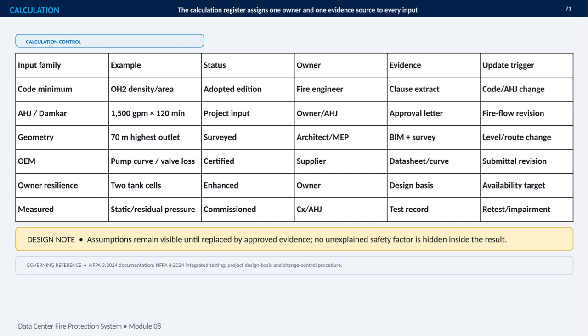Geometry relies on surveyed information, BIM and survey records. OEM inputs, such as pump curves and valve losses, come from certified supplier data. Owner resilience decisions, like using 2 tank cells, are tied to the design basis. Finally, measured values, such as static and residual pressure, are supported by commissioning test records.